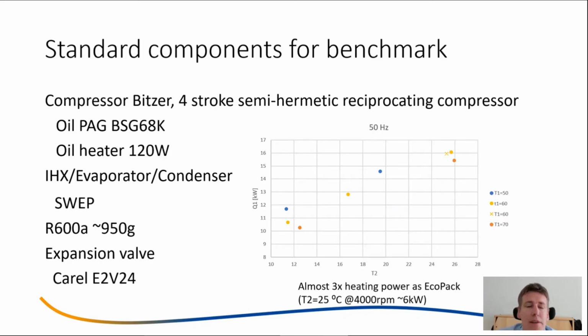But how is this compared to a standard component using a normal heat exchanger and a normal top-of-the-line compressor? To find this out, we built a similar rig that we run in parallel, and here we bought a Bitzer compressor, 4-stroke semi-hermetic, and used the oil that they recommended, which is a PAG oil. We bought a normal heat exchanger from SWEP, and these are, of course, not asymmetrical, so we needed a bit more refrigerant to make the system work. We ended up with around 1 kilo, a little bit less. We used the same expansion valve.